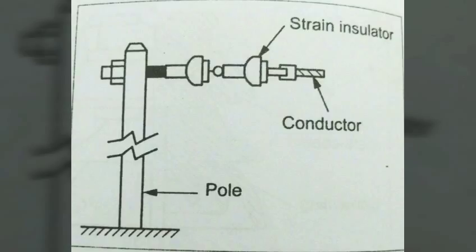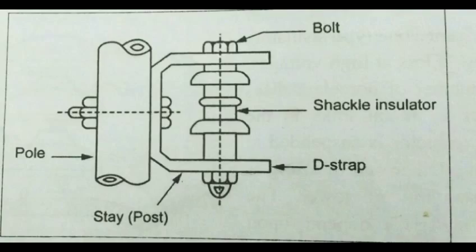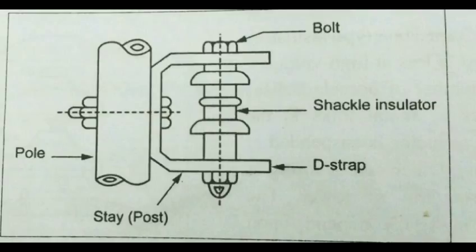Next, shackle insulators or spool insulators. In earlier days, shackle insulators were used as strain insulators, but nowadays they are used for low voltage distribution lines up to 230 volts. Such insulators can be used either in a horizontal position or in a vertical position. They can be directly fixed to a pole with a bolt or to the cross arm. The conductor in the groove is fixed with a soft binding wire.